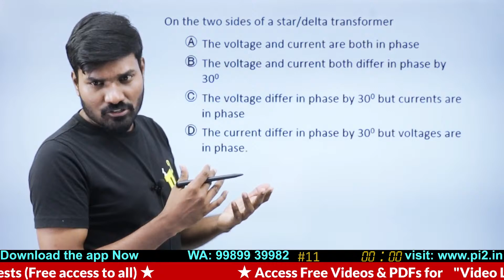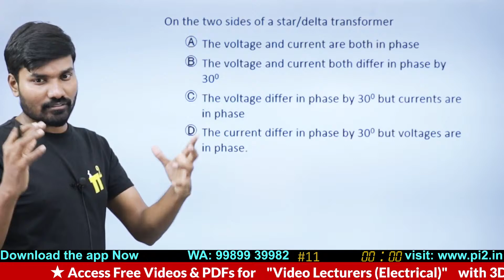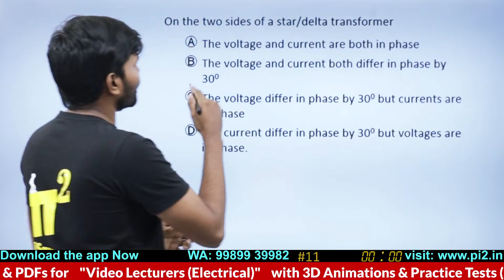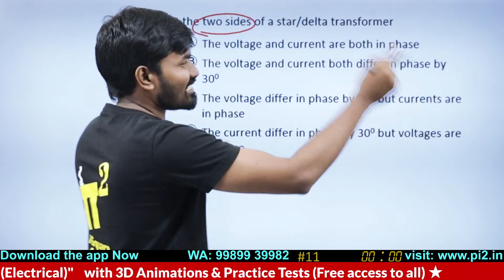Be it Scott connection or open delta connection, the numbers are important there - that's what I'm trying to say. Coming to this: on two sides of a star-delta transformer, the voltage and currents are both in phase. By 'two sides' they mean primary and secondary.